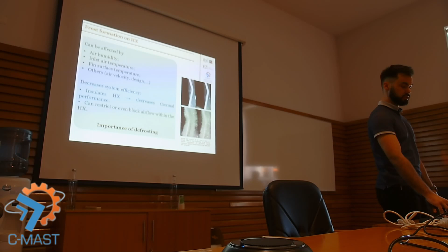To solve this problem we implement defrosting operations. There are two types of defrost methods. One is restrained frost, which reduces the accumulation of frost, either by changing the characteristics of the inlet air—for instance, dehumidifying the air results in less frost formation—or by changing the cold surface characteristics and interactions. But frost will always form, so what we can also do is remove it.